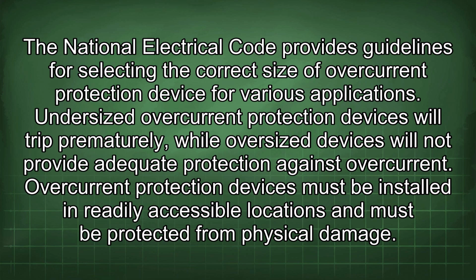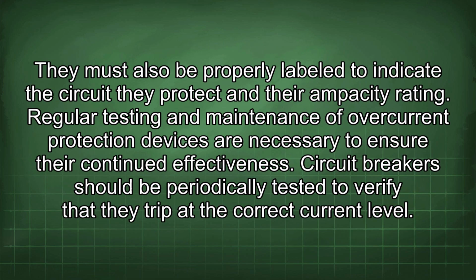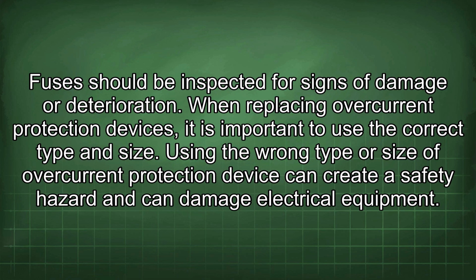Overcurrent protection devices must be installed in readily accessible locations and must be protected from physical damage. They must also be properly labeled to indicate the circuit they protect and their ampacity rating. Regular testing and maintenance of overcurrent protection devices are necessary to ensure their continued effectiveness. Circuit breakers should be periodically tested to verify that they trip at the correct current level. Fuses should be inspected for signs of damage or deterioration.